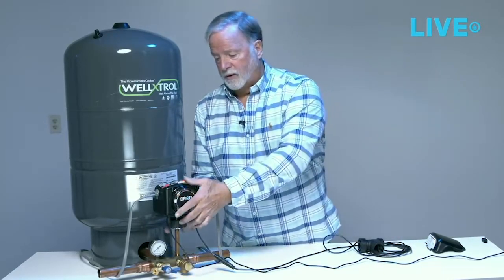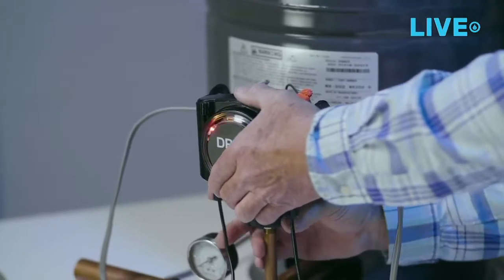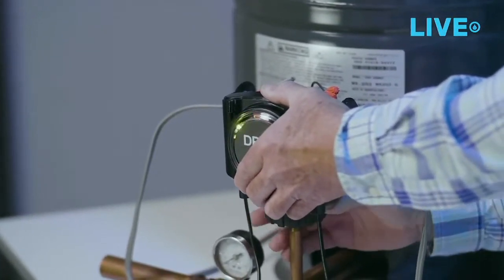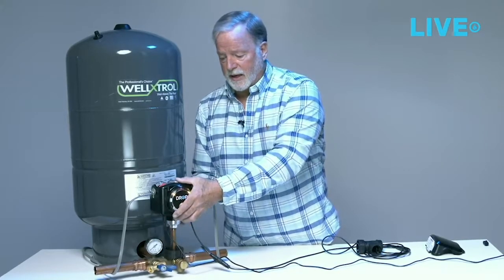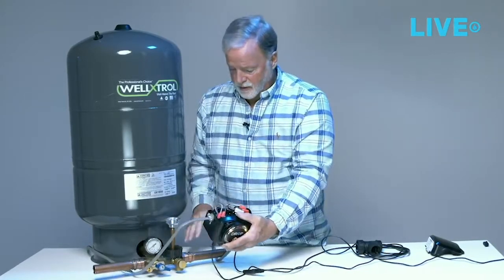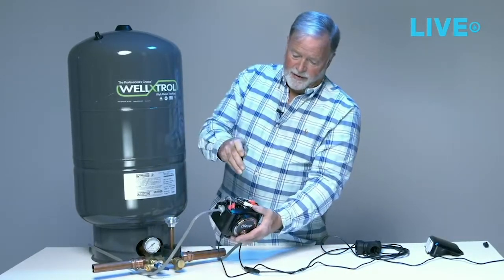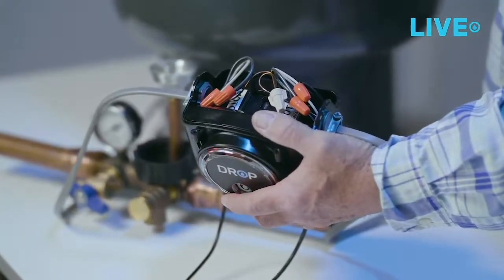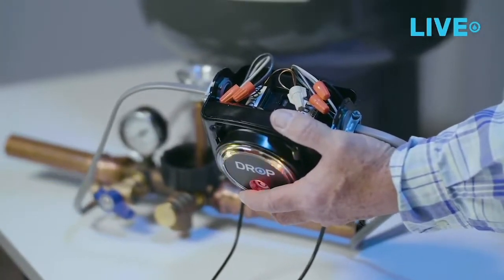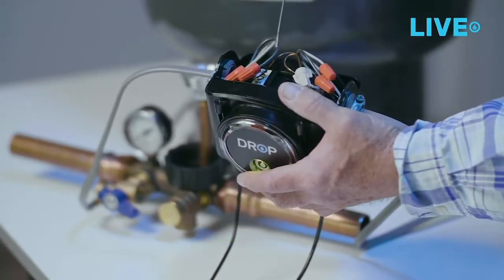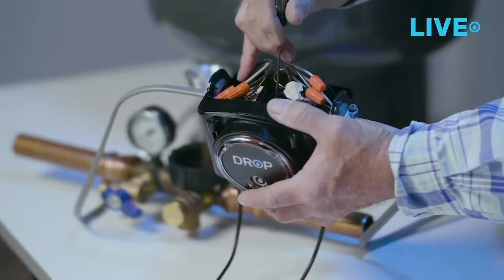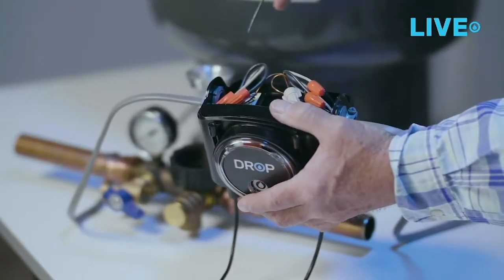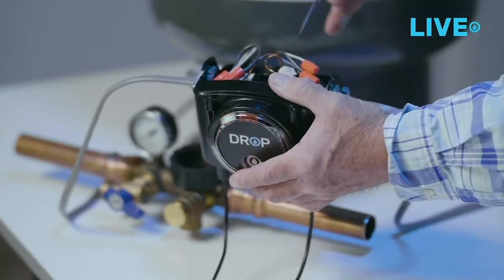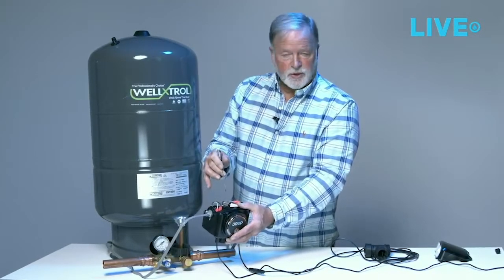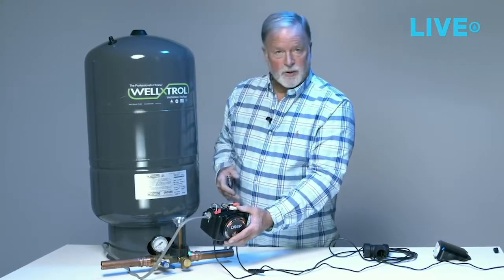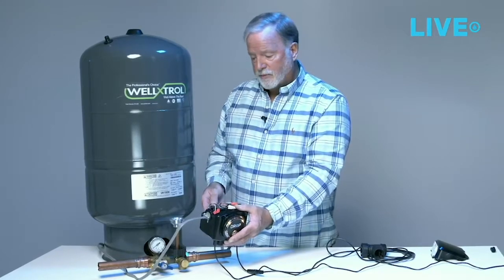We also built this unit with a NEMA contactor as opposed to an electronic pressure switch. And what that means is the mechanical contactor is very similar to a standard pressure switch that you might see on a well pump, in that I've seen a lot of service guys, the first thing they would do is mechanically push the pressure switch in to see if they're getting motor current. And unlike an electronic switch, we can merely do the same thing by actuating the contactor here mechanically. So when you step up to this unit to service it, you can just quickly push the contactor in and observe if the pump is running and watch the pressure come up and so on. Then you've isolated that the problem could be in pressure sensing.